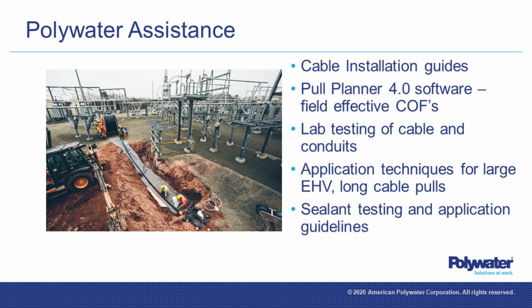You're talking about static coefficient of friction, meaning what it takes to get the cable to start moving. A good standard operating procedure is to flood or pump lubricant into the system and hook up equipment that can handle higher tension than what you maxed out on during installation. You can also do surging or thumping, rocking the cable to get it moving, since once it starts moving you don't have the same tension as during the pull-in. So I don't think this should restrict it. Worst case, at some utilities due to room constraints, you go to the vault or manhole midway, cut the cable, and pull it out from there. If the cable can't be used anymore, there are ways to remove it that won't hamper your efforts.